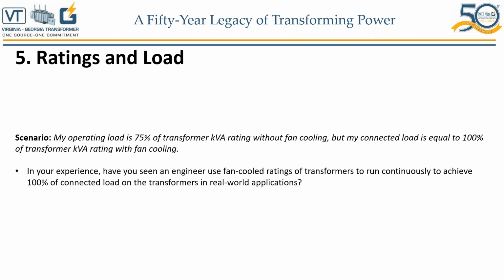So the loading and the cooling, really, what is happening in the transformer when you're loading a transformer? As we all know, there are losses, which turn into temperature, heat, right? So we have to control it with these fans, the pumps, whatever the cooling method that we use. All we are trying to do, depending on the load changes, is make sure that the average winding temperature rise and the average top oil temperature rise stay below the required levels.